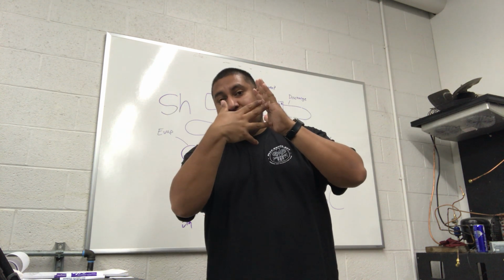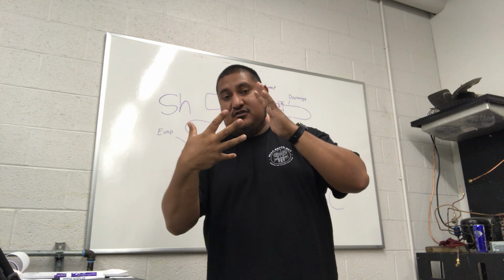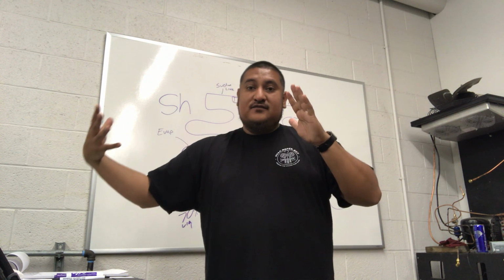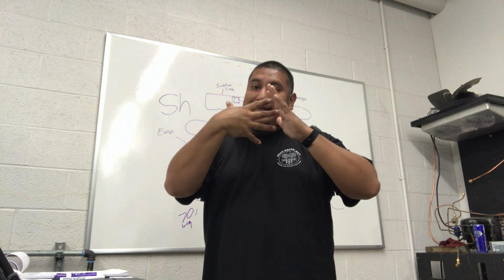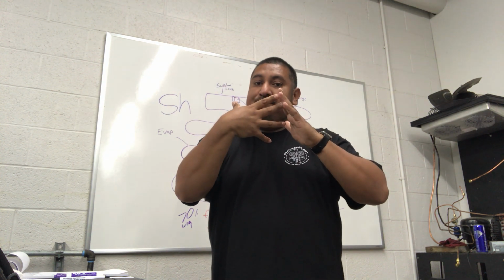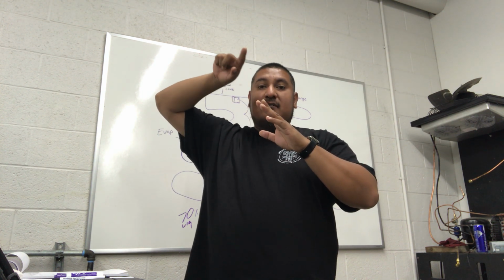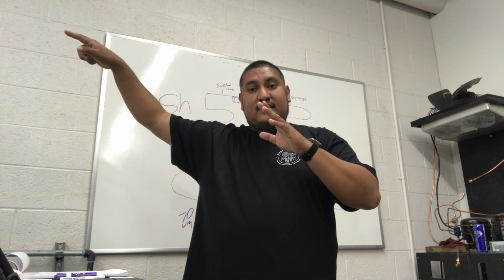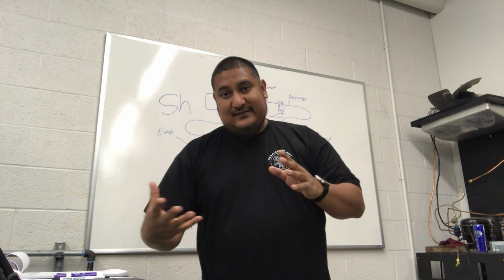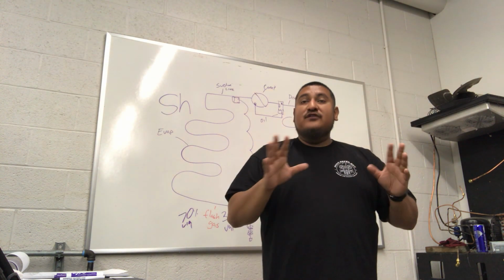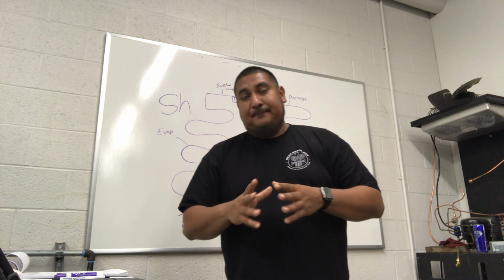The air is not going to go through it. So we have an air restriction, right? Because that warm air that can't get through it isn't giving off its heat to that coil. What's going to happen? We're going to get liquid that actually starts to climb the evaporator and then takes off to the compressor, which causes damage. So airflow is a very big issue.